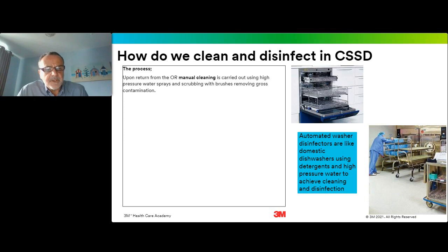So I've already mentioned, upon return from the operating rooms, the manual cleaning process would take place. And then we'd load our instruments into an automated washer disinfector, and you can see that in the top picture there. Very similar to domestic dishwashers. Obviously the process is far more rigorous, but the principles are essentially the same.